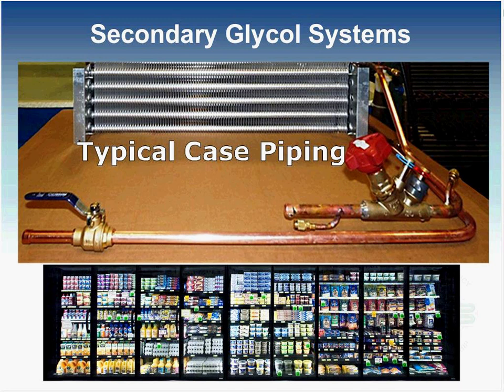But again, propylene glycol is used because typically it's a food-safe product. So if you have a leak or something and it gets spilled, you don't have any toxic fluid or chemicals in your store; it's something that can simply be rinsed down the drain. Environmentally benign, no global warming potential, no ozone depleting potential. That's correct. Cases, typically, are going to be a little bit different.